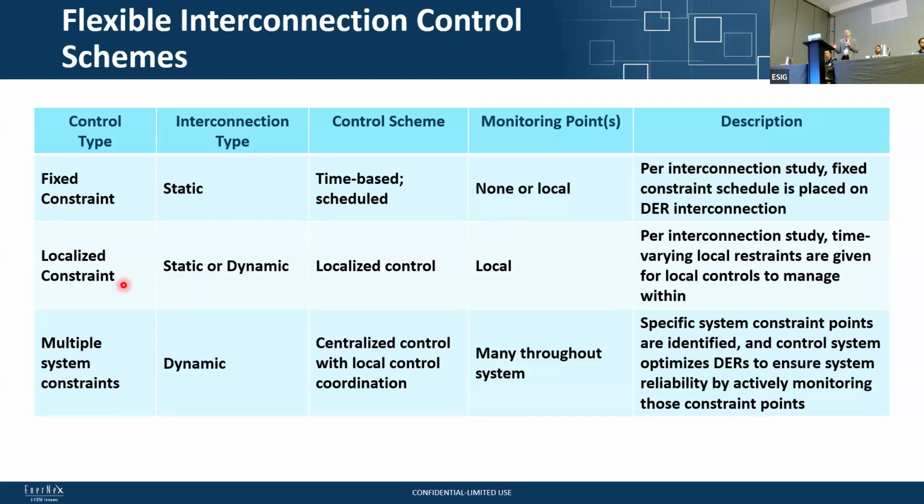So a localized constraint. This could be used for either static or dynamic, but it really is localized control, and that monitoring point is local at that point of interconnection. So whether that's a fixed schedule that it has to stay between, or actual fixed limits at that local point of interconnection, that customer is required to stay within and manage within that.